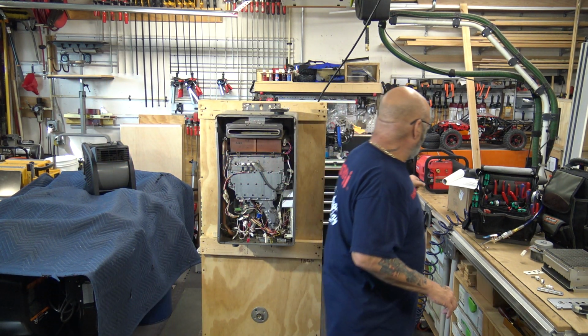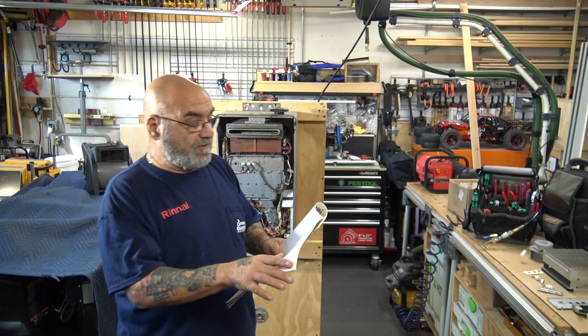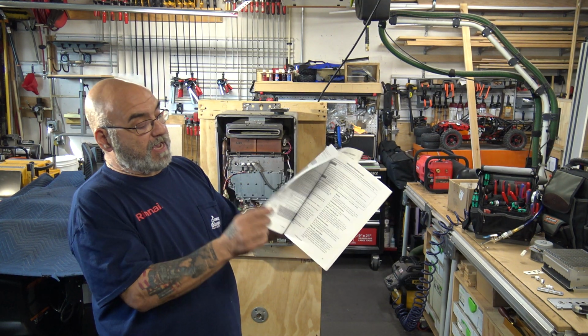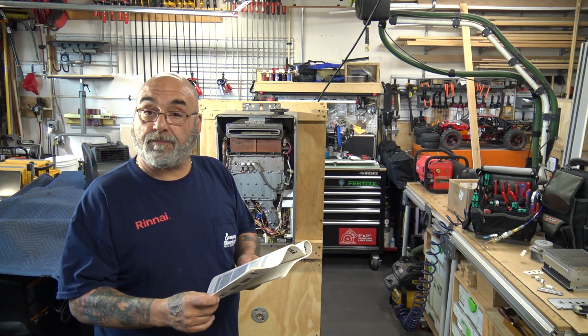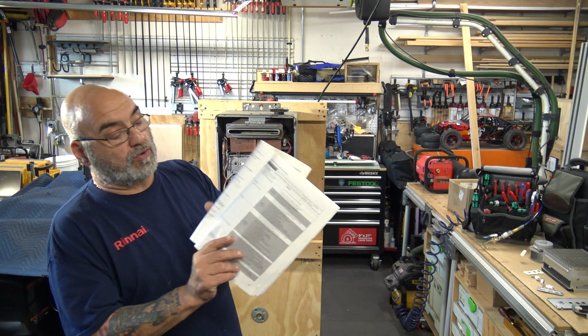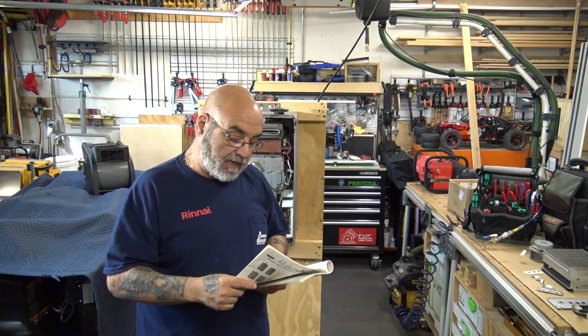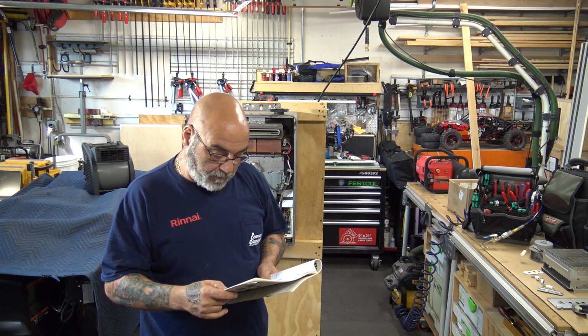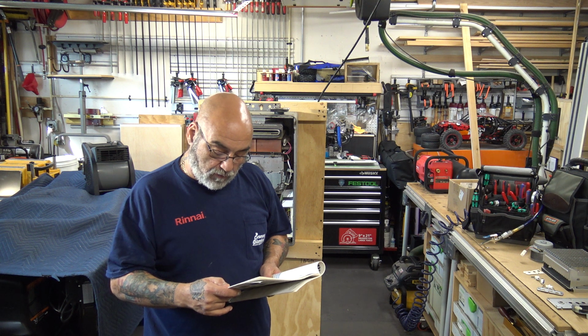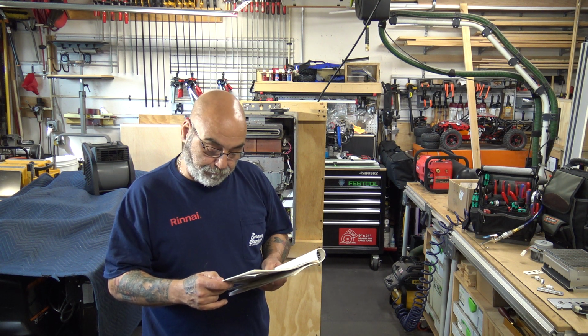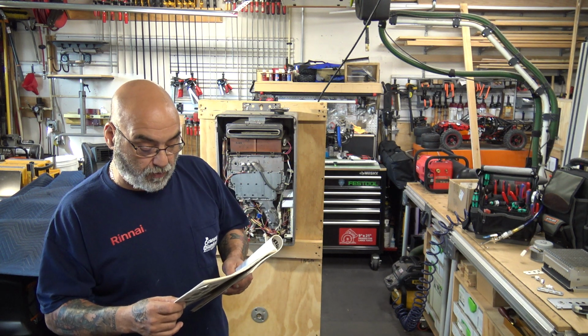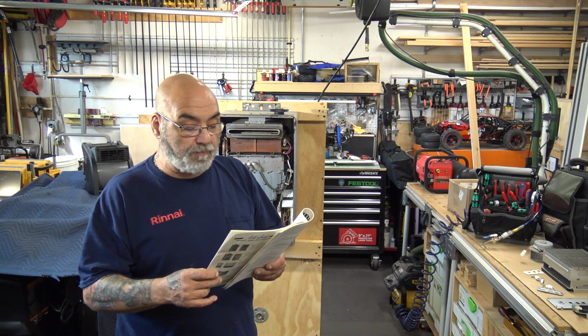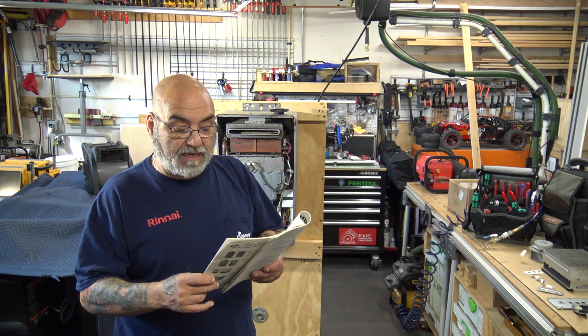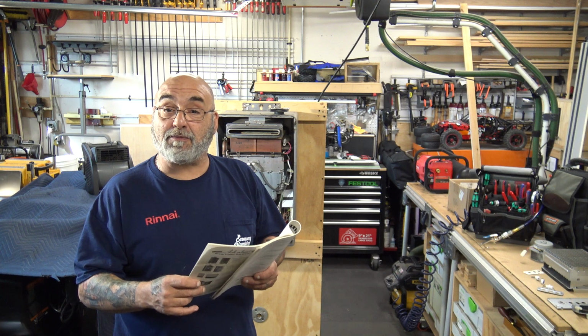In Rinnai's manual, in any of their manuals, you have pages, usually one page front and back, that has codes. Code 11 and code 12 both list, near the end, to check the burner plate and inspect the burner surface for debris—actually condensation or debris. On code 11, it says remove the burner plate and inspect the burner surface for condensation and debris.